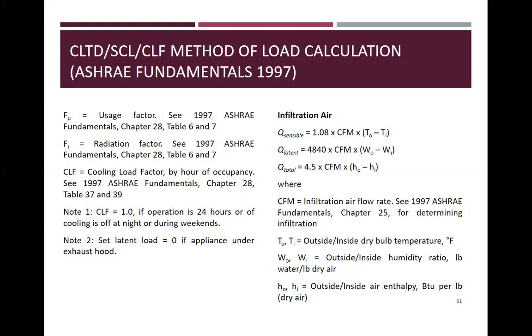Okay. So CFM is equal to the infiltration air flow rate. See 1997 ASHRAE Fundamentals, chapter 25 for determining infiltration. T is the outside and inside dry bulb temperature. W is the outside and inside humidity ratio. H is the outside and inside air enthalpy per pound of dry air.